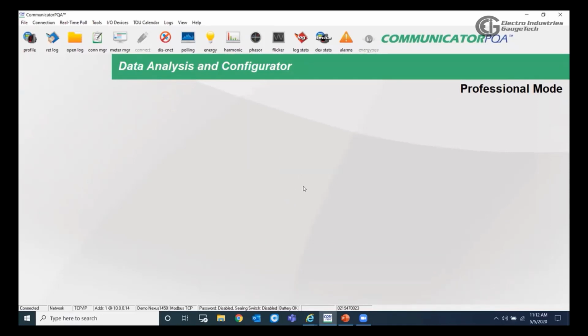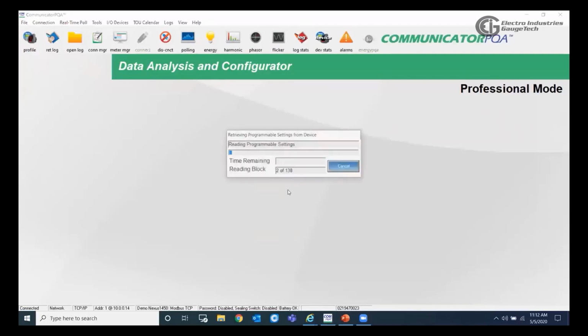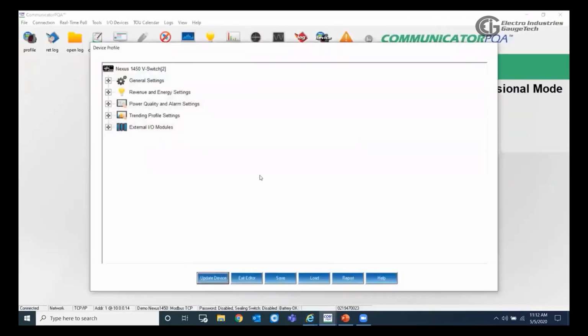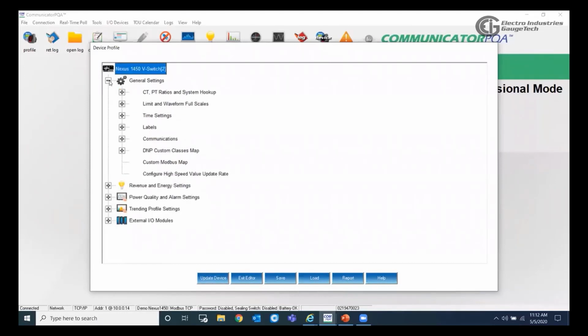Now we will talk about how we can do the basic programming and the default profile, and how we can do the CT-PT ratios and all the basic programming of the 1450. After we get connected with the meter, we will go to profile here. And after we got the device profile window pop up like this, we have the model here and the vSwitch. And on the tree menu, we will go to the general settings.